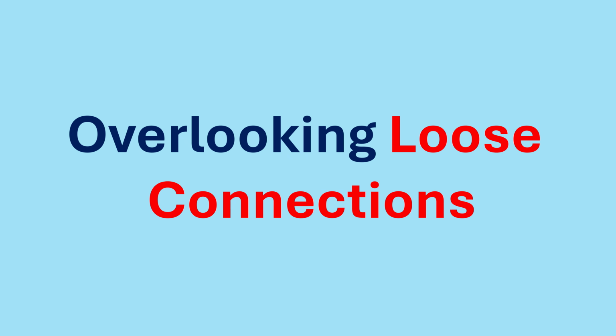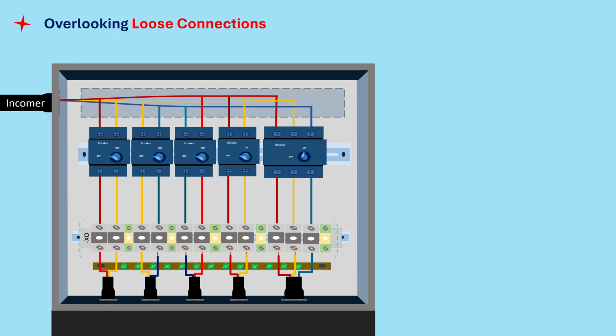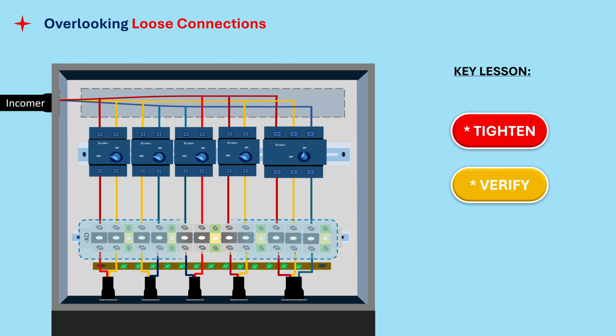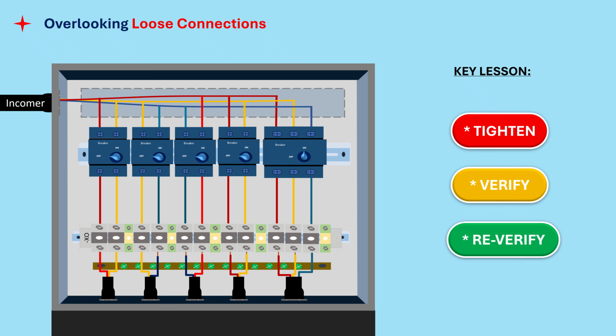Mistake number 5. Overlooking loose connections. Loose terminals create the most frustrating type of electrical problems, the ones that come and go. A machine may run perfectly during testing and then fail once it's vibrating or under real workload. Gently retightening each terminal during installation or maintenance can prevent these hidden issues and save hours of downtime later. The key lesson from mistake number 5 is simple: tighten, verify, and then re-verify every connection.